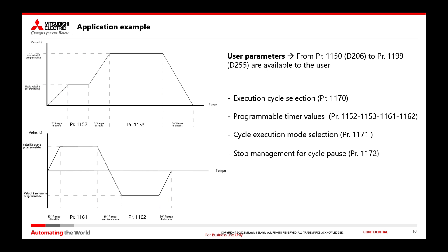Before concluding, I wanted to show a more advanced application example to give an idea of the potential of the integrated PLC. The parameters available to the user have been used to create different functions. Parameter 1170 allows you to select the machine cycle between the standard one and the one with a reversal of direction. The various parameters for the programmable timers, which in addition to being retentive, resume from the stored value in the event of a stoppage, also allow the user to decide the time interval at constant frequency. Parameter 1171 allows you to select the cycle execution mode: if it's 0, it's executed only once; if it's 1, it's executed in loop mode.